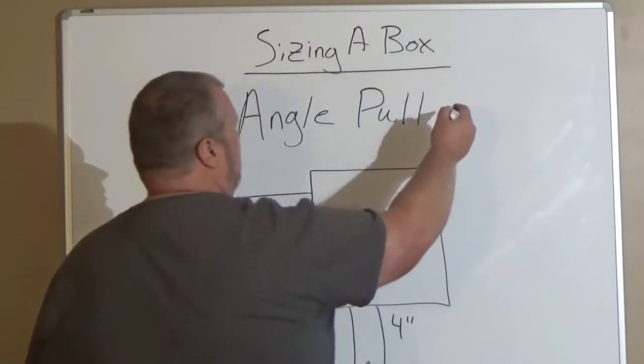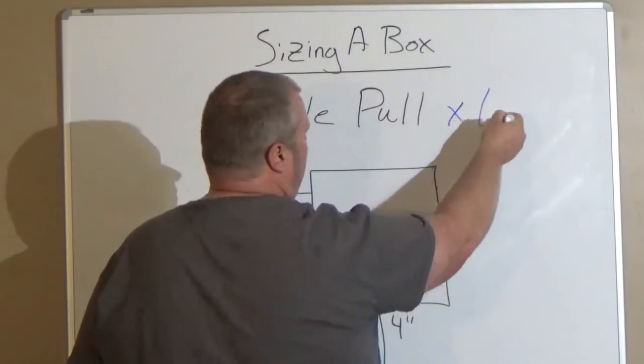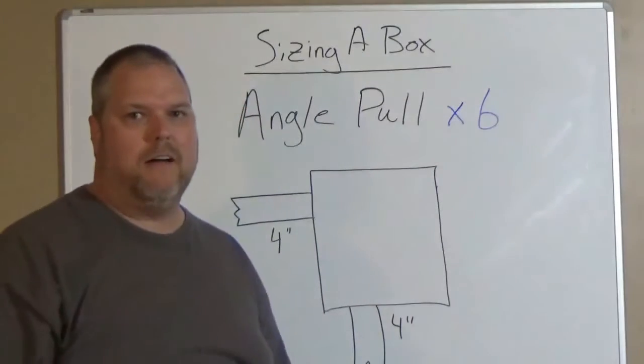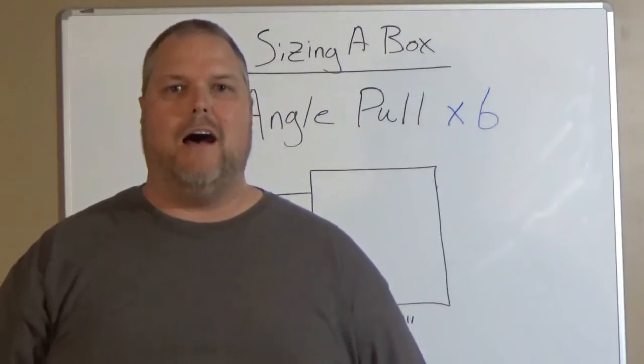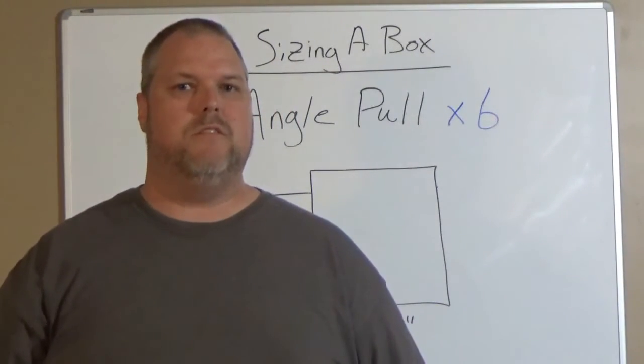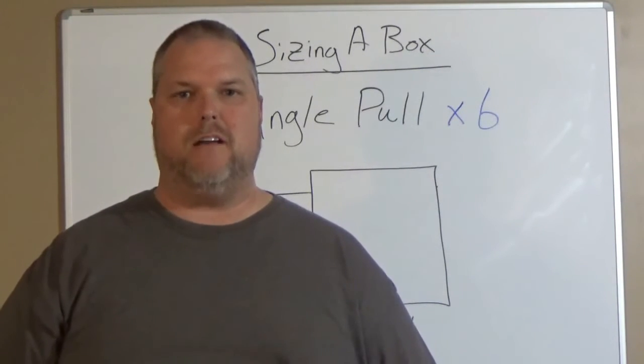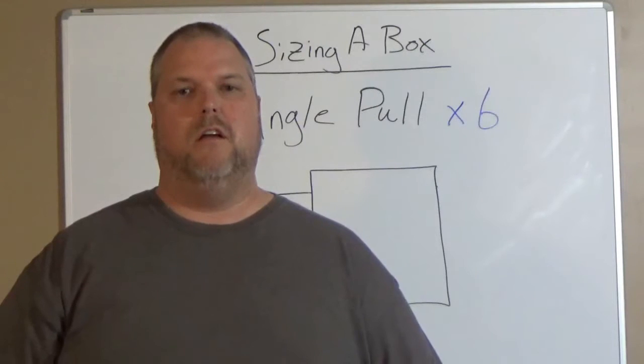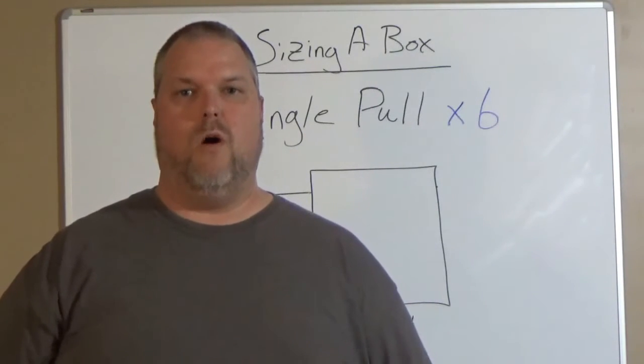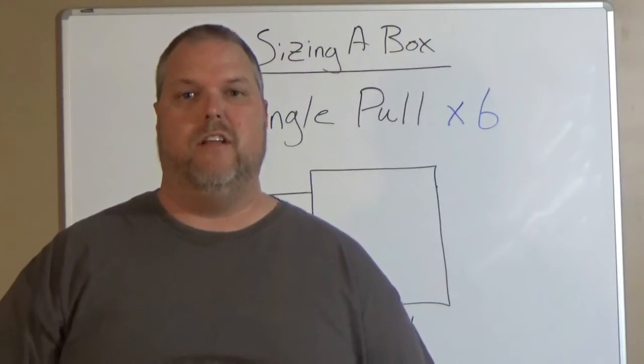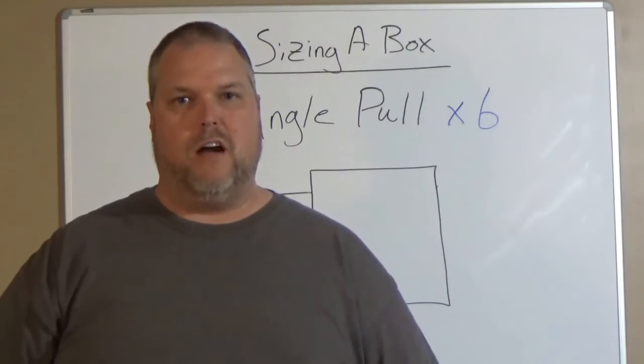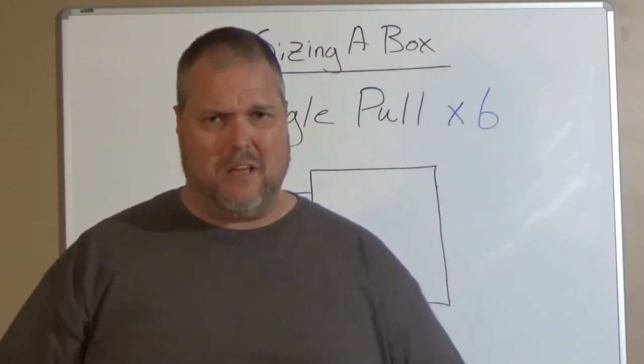So we will multiply a pull box or an angle pull box that will be sized 6 times the largest conduit. Sizing the junction box to the conduit. How we size the conduit to the wires will be done in a later video. So please keep a look out for that one. Let's get back to this.